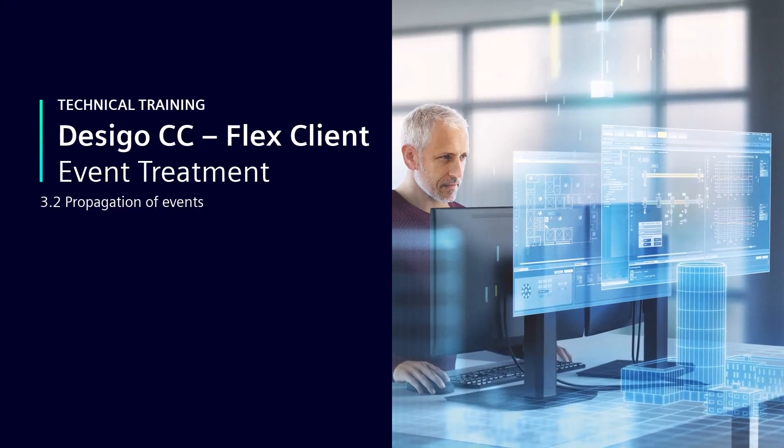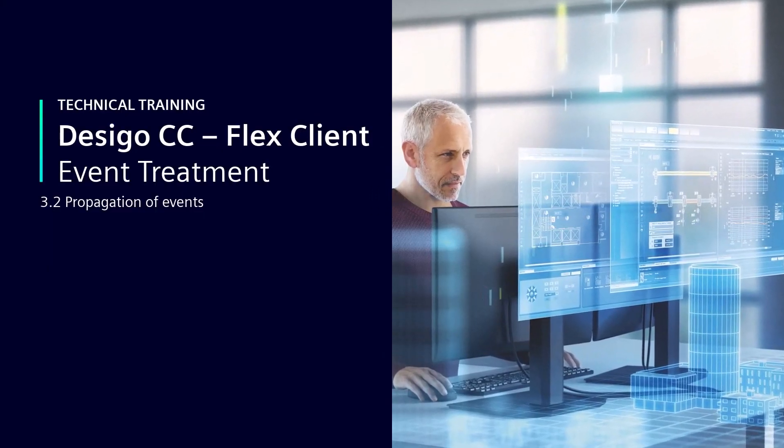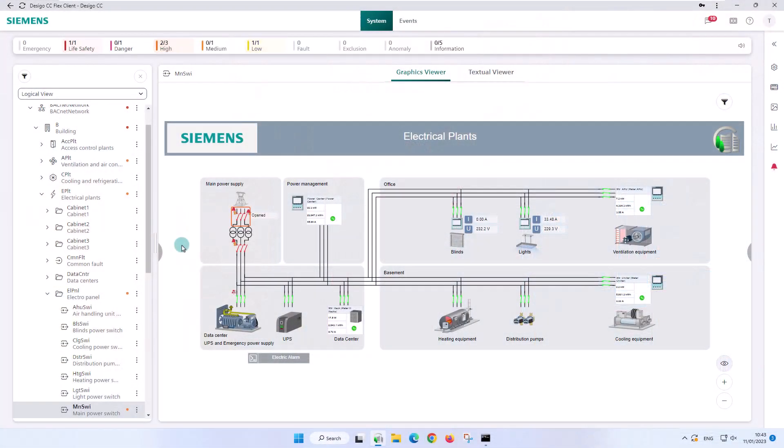Propagation of events. Another specialty of the FlexClient is the propagation of events in the system browser tree. Propagation means relaying common status information up the building hierarchical tree of the management platform.